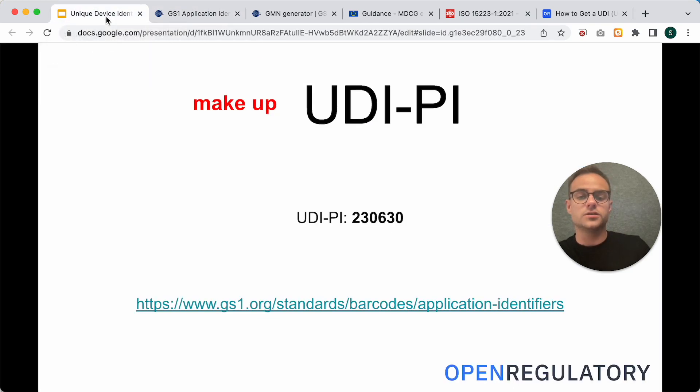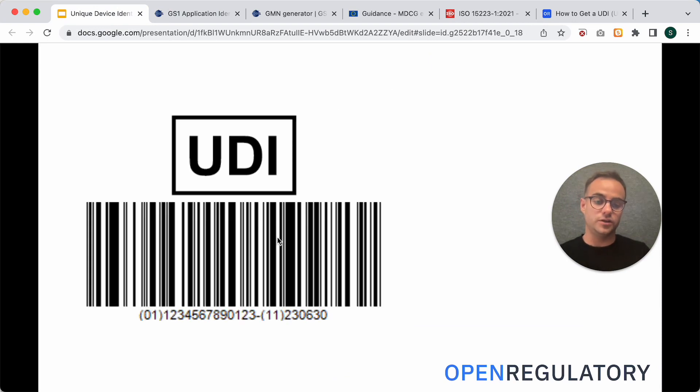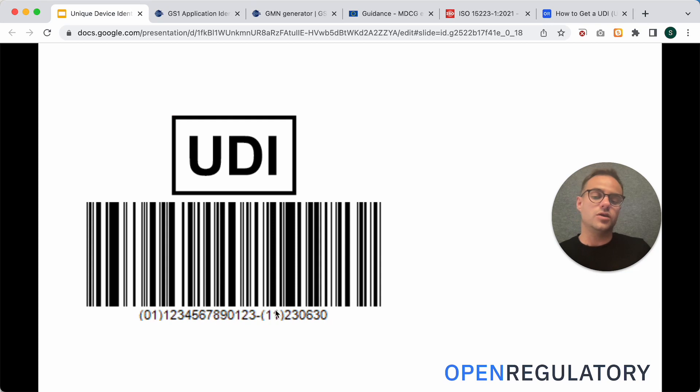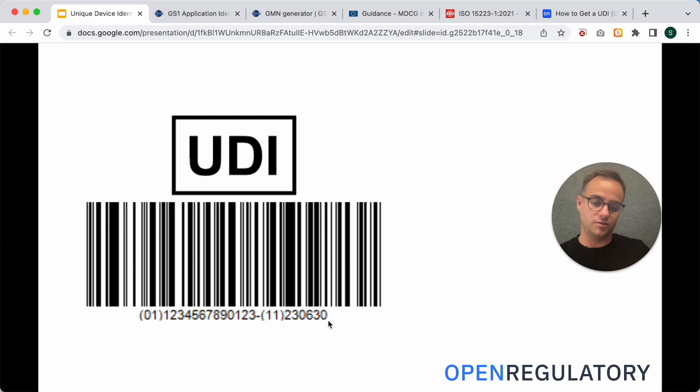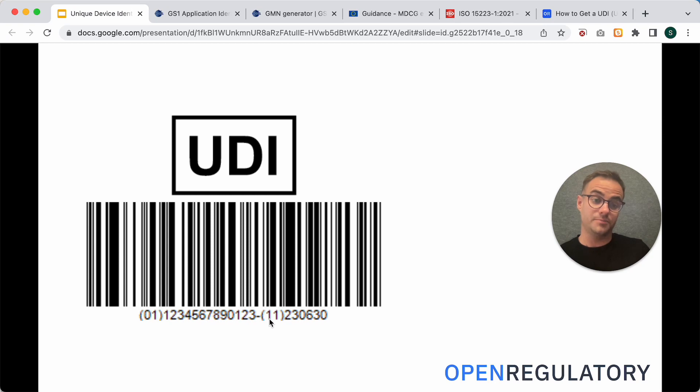And it has the application identifier 11. So, when we look at our finished UDI, you can see here that you have an 11 that's signaling, okay, here comes a production date, and then you have the production date here. That's your UDI-PI.